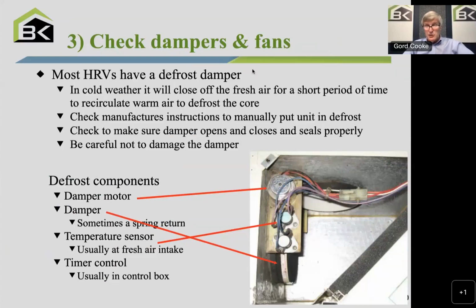There will be a temperature sensor, not typically something that you can fix. The damper motor, something you can fix. Typically never need to change the damper blade, but sometimes the temperature sensor will go, and that's typically a service item. And how would you know? Well, I'll show you in a second as to how you would know that that is true. And the timer control is typically back in the control box based in electronics. Nothing you can do to service that.